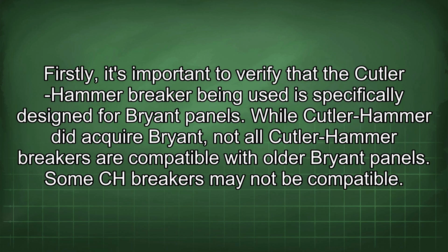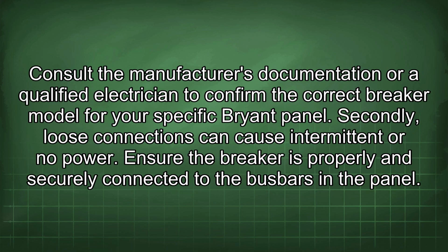Firstly, it's important to verify that the Cutler-Hammer breaker being used is specifically designed for Bryant panels. While Cutler-Hammer did acquire Bryant, not all Cutler-Hammer breakers are compatible with older Bryant panels. Some CH breakers may not be compatible. Consult the manufacturer's documentation or a qualified electrician to confirm the correct breaker model for your specific Bryant panel.